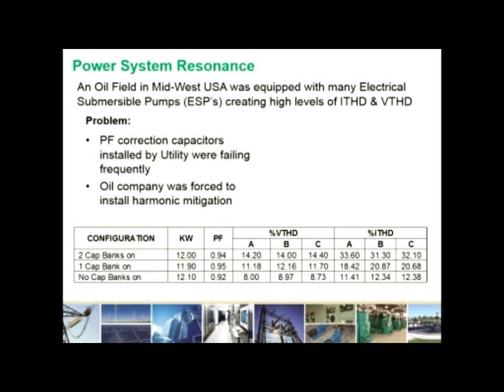This is an oil field in Midwest USA that was equipped with a lot of electrical submersible pumps, or ESPs. The utility saw that the power factor was low and forced the oil company to install power factor correction capacitors in an attempt to improve the power factor. When Mirus was brought on board, it was after the utility noticed that the distortion levels, both voltage and current distortion levels, were high, and they then forced the oil company to install harmonic mitigation equipment.